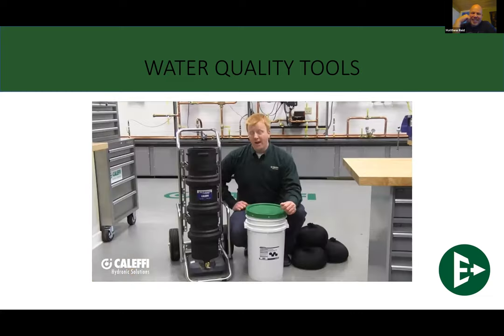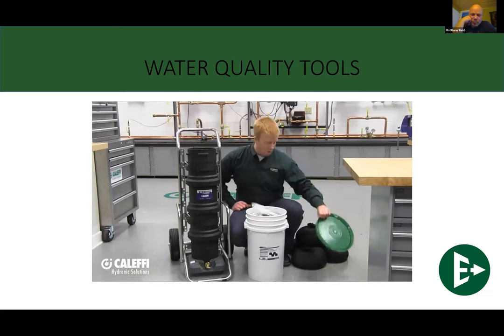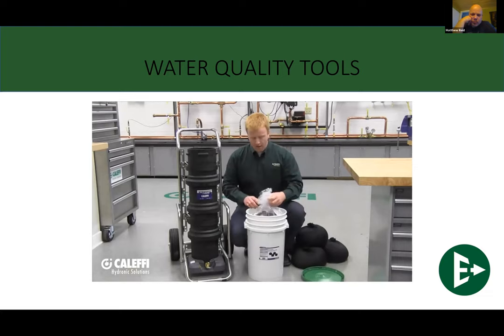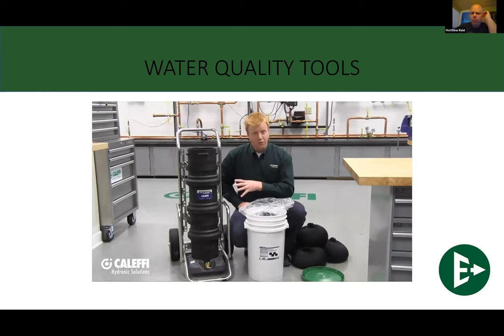Your replacement bags are going to come in a nice tightly sealed bucket that we've got here. This bucket is a 4 bag replacement bucket. You'll notice that when you pull the bags out, they're going to be quite damp. It is very important that these resin bags remain damp and don't dry out completely, as it will reduce the effectiveness of the resin bags. The same thing holds true when you go to stop using the Hydrofill unit. You're going to want to drain out most of the water, but close off the valve at the bottom and put the cap back on.